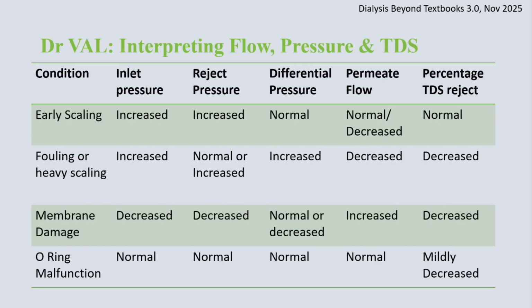If there is a membrane damage, then the pressures are all decreased because there is a free flow through a membrane which is damaged. The permeate flow is increased, but the TDS reject is very low, or in other words, there is a very high conductivity or no change in the inlet conductivity and the outlet conductivity of the RO.